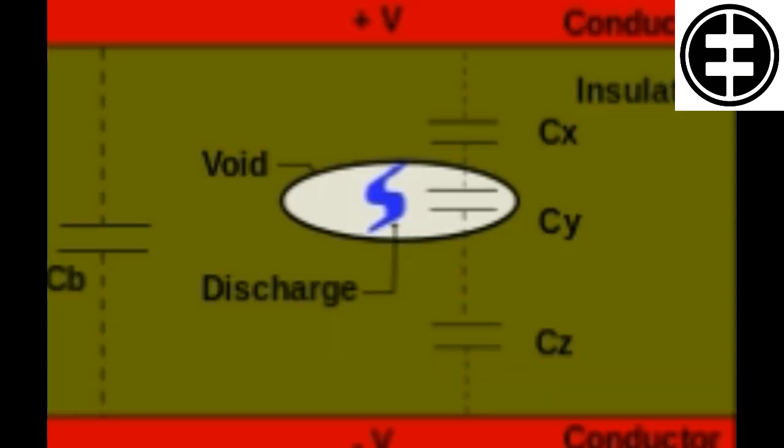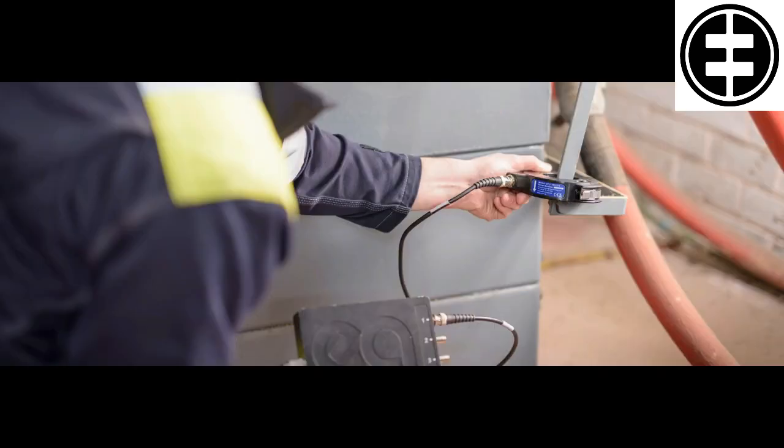Internal PD generally occurs in microscopic air-filled voids that remain inside the insulation, with the number and size of the voids depending on the procedures followed during manufacturing. Charges build up around the voids and when the local electric field stress across a void exceeds the breakdown field stress, a discharge occurs that short circuits the void. Special equipment is required to detect and measure internal PD.